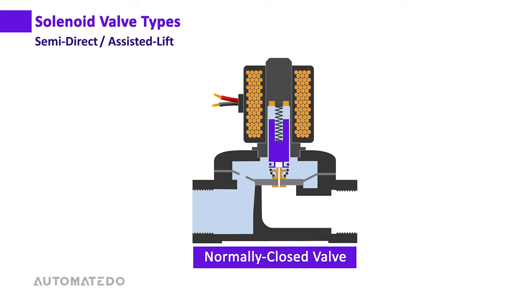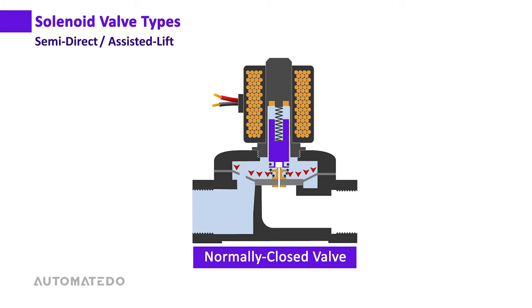In a normally closed semi-direct acting valve, two chambers are separated by the diaphragm. A tiny hole connects the chambers, equalizing pressure in both. The media in the upper chamber contacts a larger diaphragm area than the media at the inlet, so the diaphragm is forced down toward the valve seat and the valve closes.